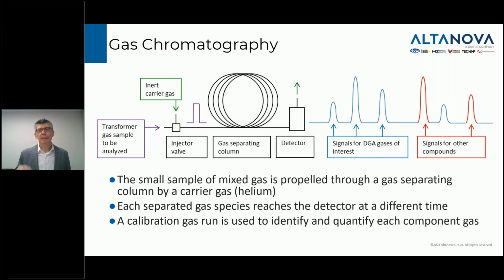And the inside of that column contains a chemical coating or powder, which has not too strong, not too weak chemical interactions with each of the gas species that are involved here. And the net effect of that is that different species travel through this column at different rates, so that each one reaches a detector at the end of the column at a different point in time. And so that's shown here in this image as these peaks, these blue and red peaks that are coming out. This is meant to indicate the chromatogram, which is the raw data that comes out of a GC.